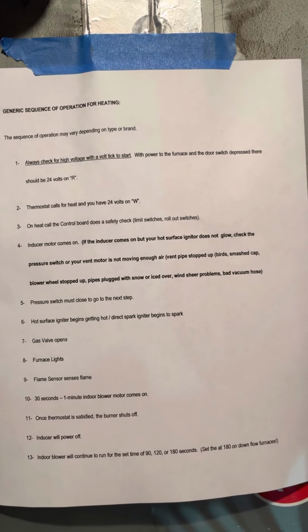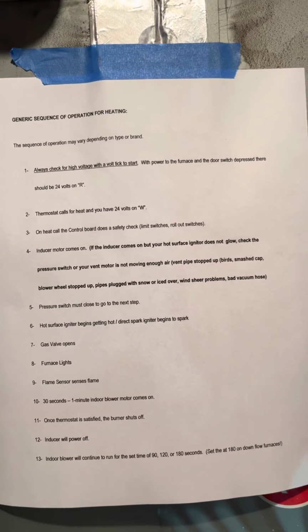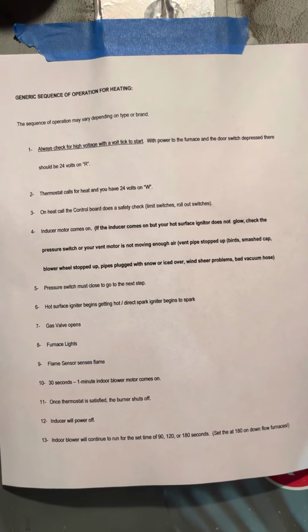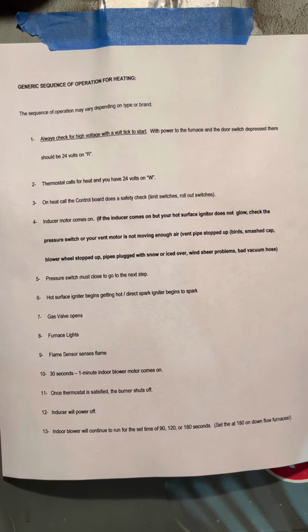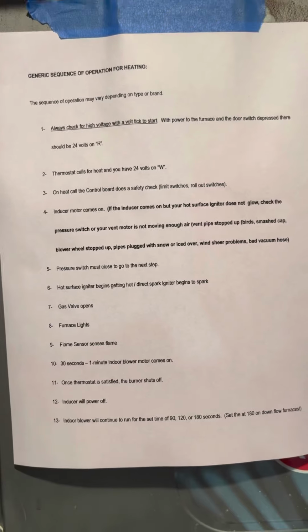you'll get spark or hot surface. You'll get the gas valve opening. You'll get main burner. Flame sense will take place, telling the board that there is indeed flame, in order for the gas valve to remain open. And then after the timer goes through its time, whether that's 30 seconds or 1 minute, for the heat exchanger to warm up, the indoor blower will come on, and it'll run until the thermostat's satisfied, which the thermostat will then open, and there'll be no power on W.